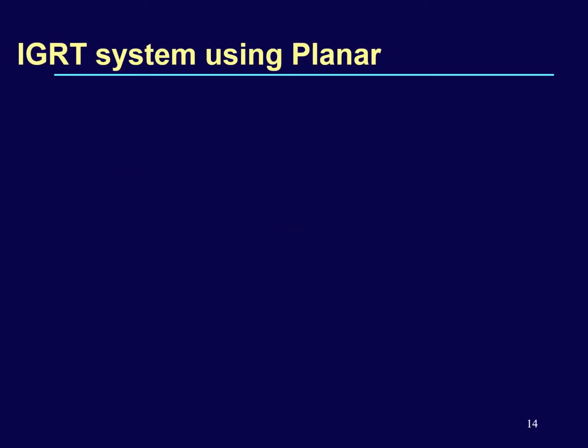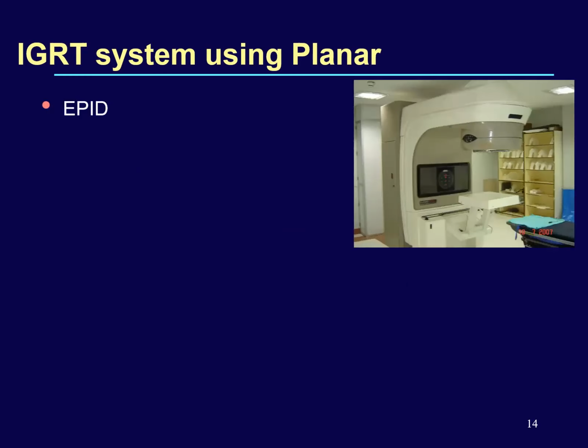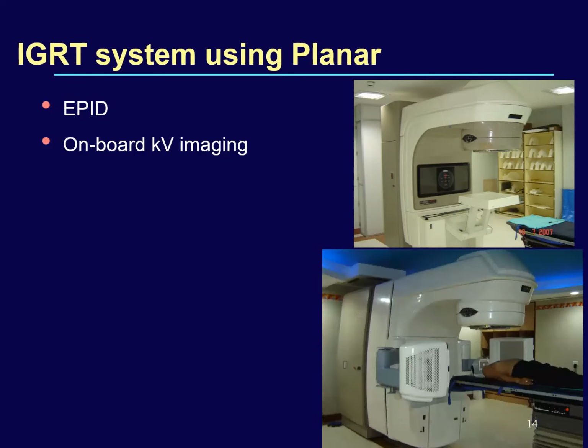Now coming to the planar imaging used for IGRT. The electronic portal imaging initially started with the video camera based system. Later, matrix ion chambers were explored. And finally, the amorphous silicon flat panel detector, which was able to offer good quality images with high resolution, became the standard of care. And this could provide you MV portal imaging, and having two orthogonal portal images, one can have 3D data. The next one was the onboard kV imaging, which means they mounted a kV X-ray tube and a flat panel kV detector at an orthogonal angle to the MV beam.